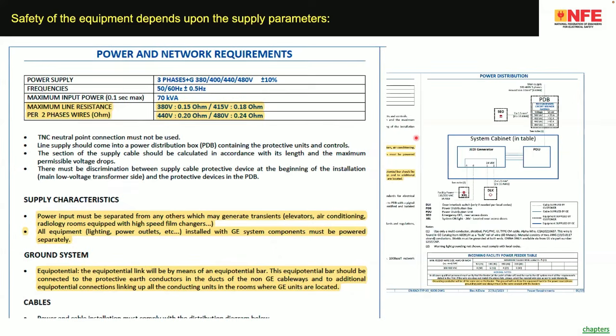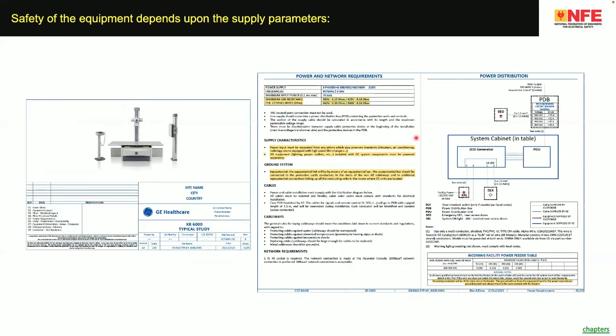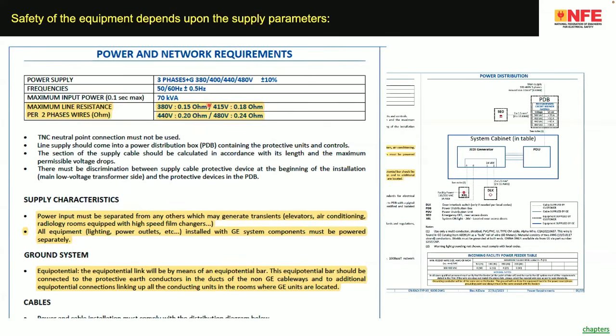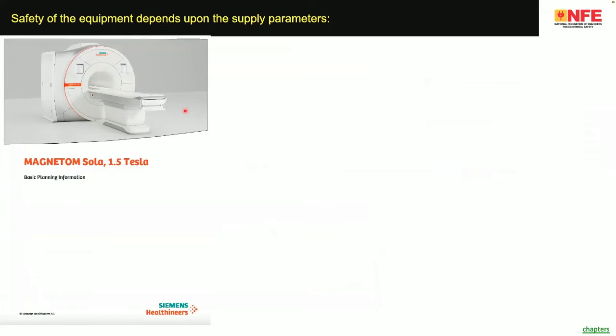You can also find the information in the manuals of most of the manufacturers. Example, this is a GE, one of the equipment you can see here. I just highlighted some of the subjects. Maximum line resistance: this equipment is 70 kVA and the line resistance mentioned is 0.15 ohm. That same line resistance, the new modern word is line impedance. Before installing this X-ray machine, the biomedical engineer or the equipment supplier is supposed to check the line resistance and ensure that it is less than 0.5 ohm. If the line resistance is more, of course, this equipment will create danger.